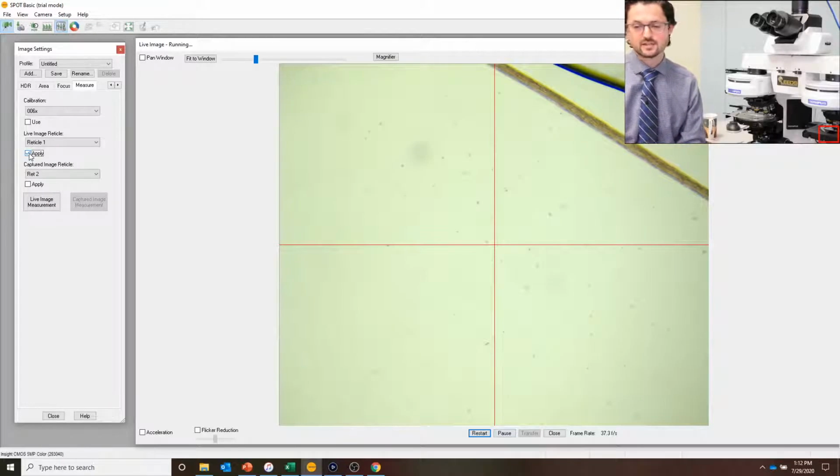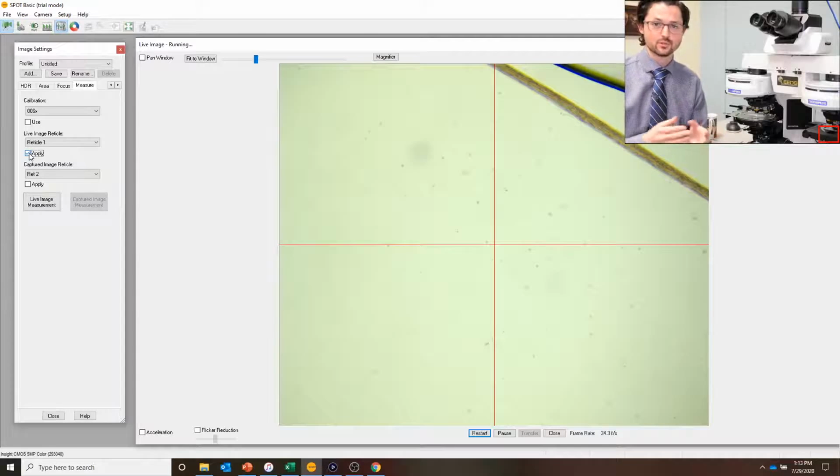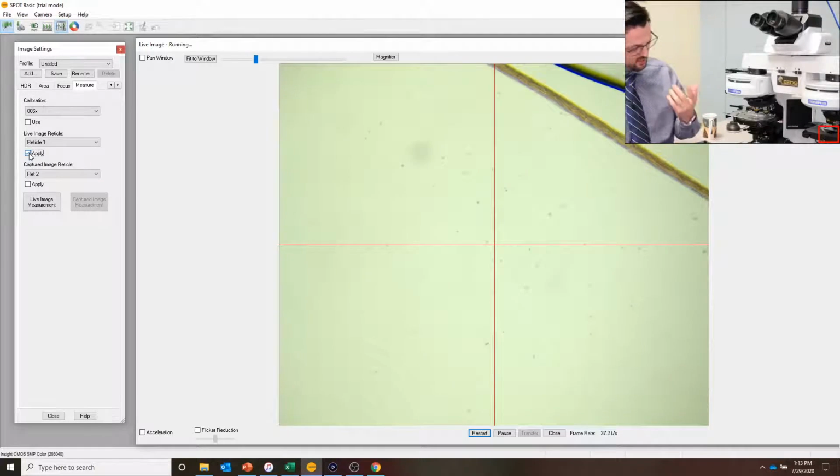It also comes, and I was talking to Kevin Boulay, who has a lot more experience than I do with these particular applications for geology. And really what it is oftentimes when you're doing qualitative work, you'll be using the highest numerical aperture lens you have. And that's usually a higher magnification lens. And so that's where you're also going to really want to make sure that those objectives are in their centerable positions.